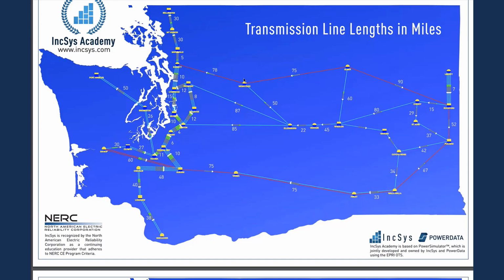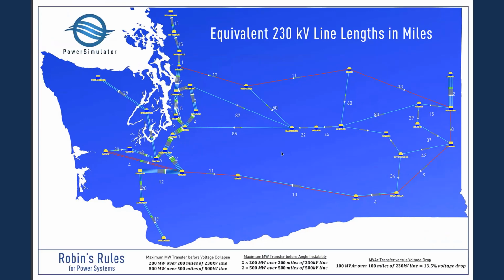And the system has a 500 kV backbone in the red, along with the cyan or blue 230 kV. And as we saw in the previous module, we converted that to these equivalent 230 kV line lengths, or the electrical distance diagram. So what we'll do is run the simulator and look at the impact of switching a shunt reactor at this station in Elma and also at this station in Walla Walla.